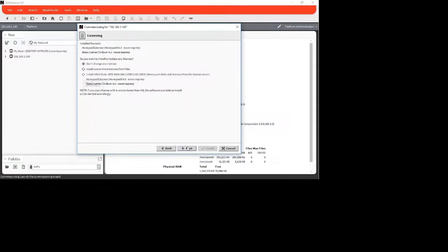First of all, if you do not have a license, you can search for it on the server once your computer is logged in. If you purchased your JACE properly, it should be on the server of Tridium, and then it'll find it and install it. Once you've installed it already, it says it's already there, so you don't need to change it. At this JACE we won't, but in commissioning a JACE you check here, so we can search and find it, or if you had it on your computer, you'll be able to install it manually. Continue.